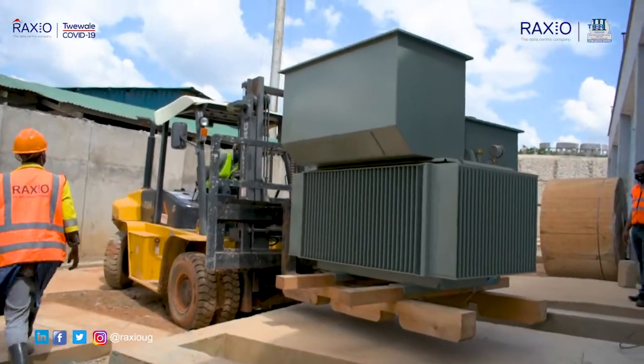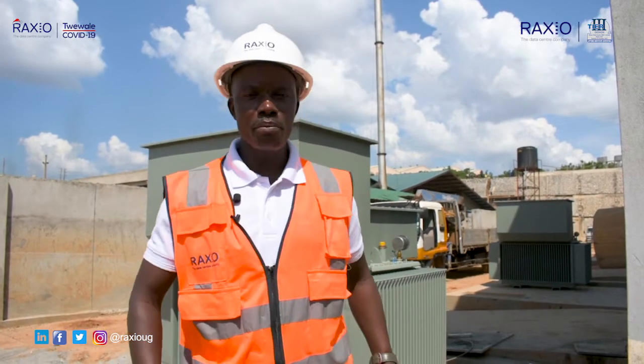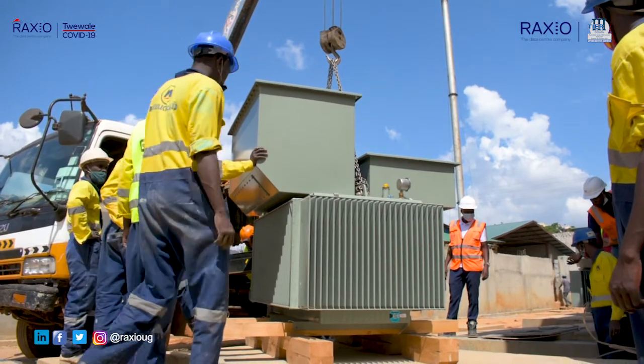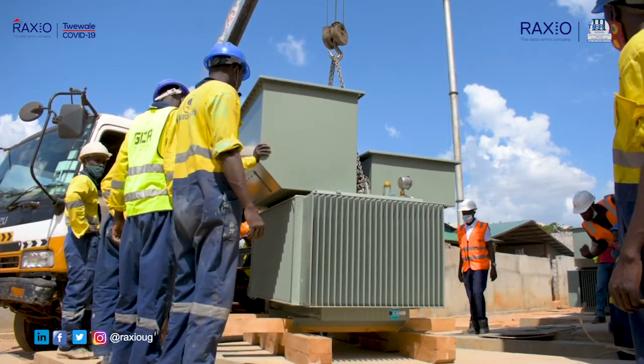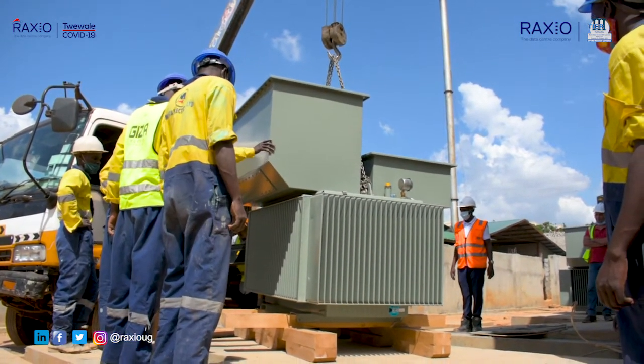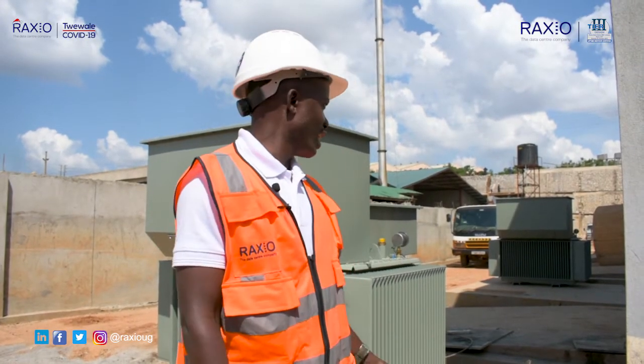We have generators, of course, in N+1 configuration. Transformers have also been installed on their bases in N+1 configuration to satisfy the Tier 3 requirements. So we are going to integrate the systems - the generators, the transformers, the power kit in the HV room, that is the HV switchgear. And as you know, we have 2 power rooms.